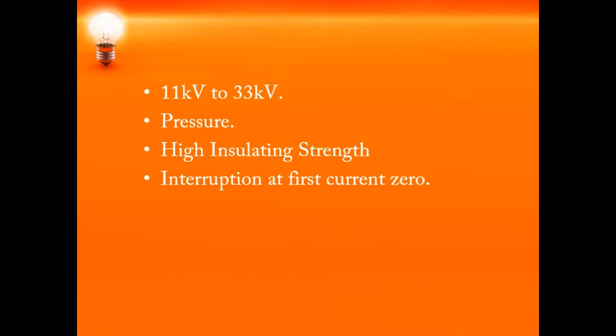When the arc is formed, that is, when the contacts in the circuit breaker get separated, the arc will get interrupted at the very first current zero. When the arc is quenched at current zero, the dielectric strength increases very much, around 1000 times when compared to other circuit breakers. That is why the vacuum circuit breaker is very good. The high insulating strength and the ability to quench the arc at the first current zero make the vacuum circuit breaker more efficient.